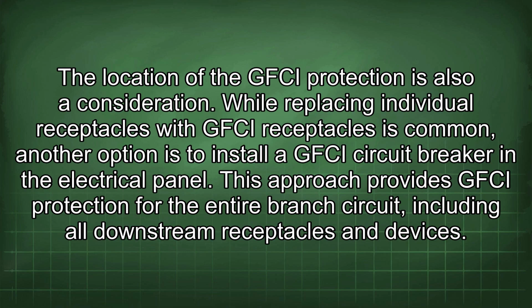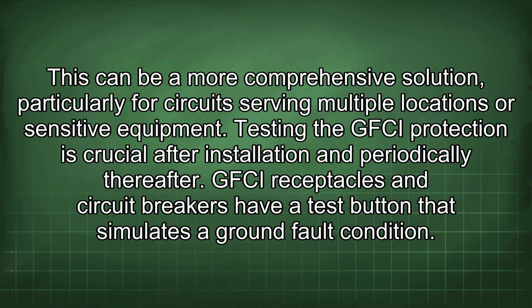While replacing individual receptacles with GFCI receptacles is common, another option is to install a GFCI circuit breaker in the electrical panel. This approach provides GFCI protection for the entire branch circuit, including all downstream receptacles and devices. This can be a more comprehensive solution, particularly for circuits serving multiple locations or sensitive equipment.